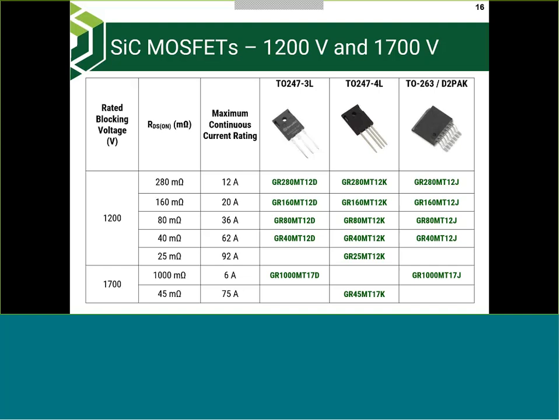Where are typical applications, and what frequency are they used at? For lower power levels, let's say less than 10 kilowatts, I'd hazard a guess it's in the range of 150 to 200 kilohertz. On the higher power side, it's more like less than 100 kilohertz, maybe 75 to 100 kilohertz. Of course, some applications use these devices even at 20-30 kilowatts at 150-200 kilohertz, but if I had to pick a median, it would be around 75 kilohertz for more than 10 kilowatts, and 150-200 kilohertz for less than 10 kilowatts.